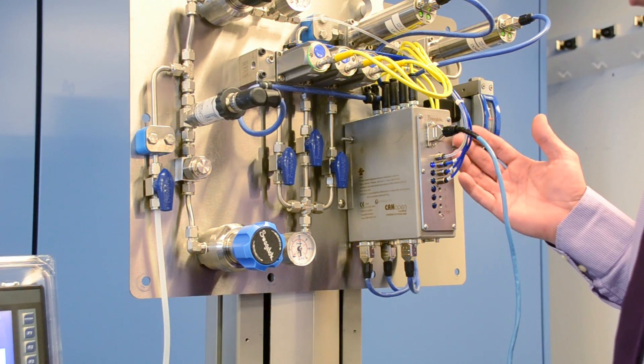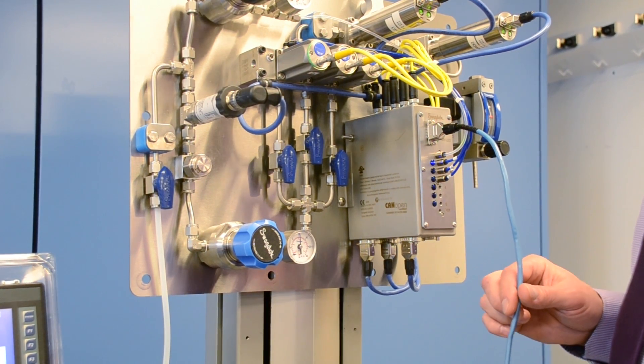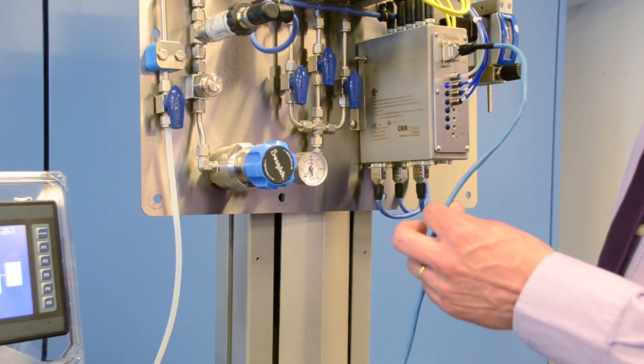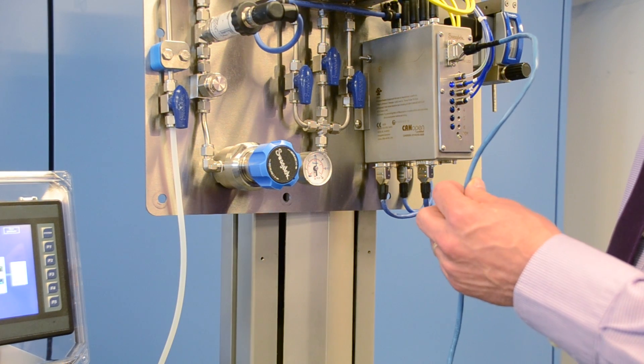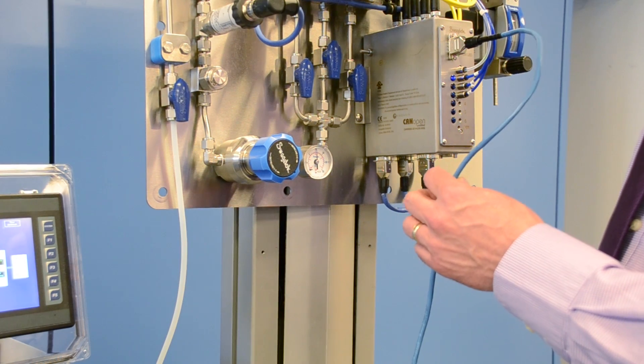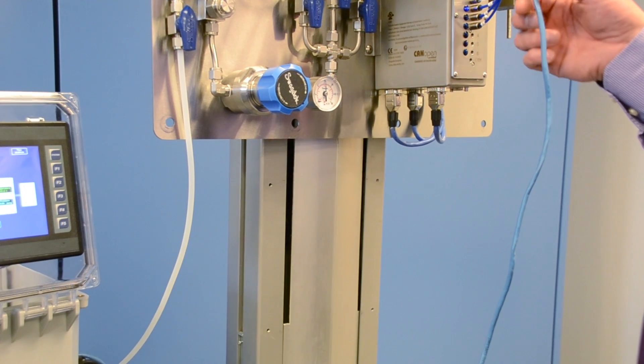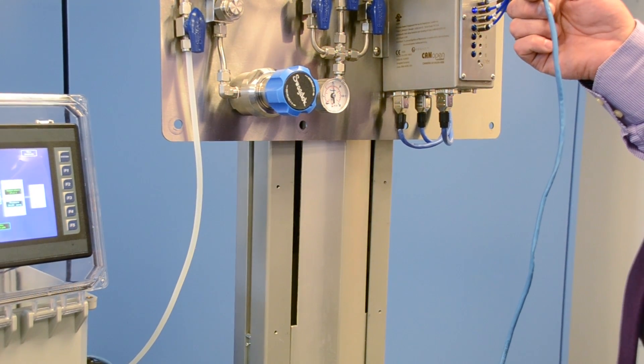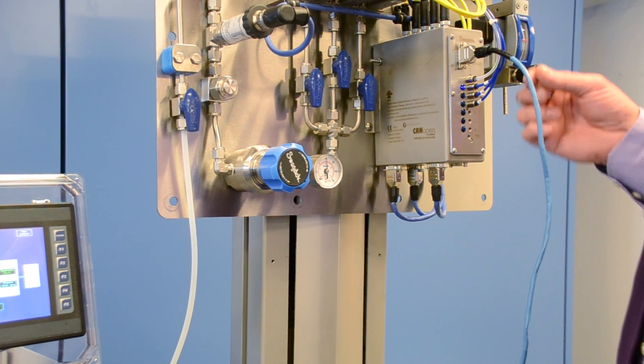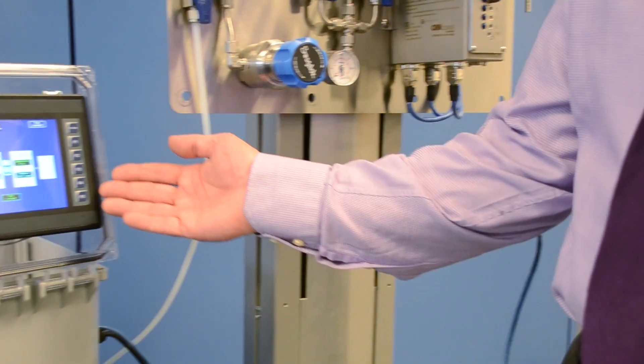All of the data that the Intelligent Control Module collects from a sample system is made available on a network interface. This network interface is intrinsically safe, this being the only electrical connection to the fluid system. Both power and communication are present inside this wire, and this intrinsically safe digital data makes its way through this cable, and actually the network that is used by the ICM is an open standard CAN-OPEN interface. That data makes its way down this cable, and ultimately over to our operator control station.